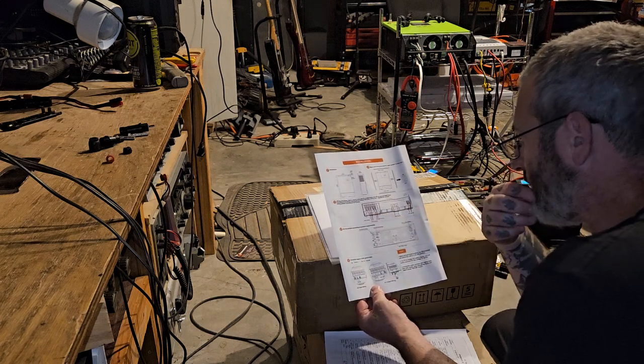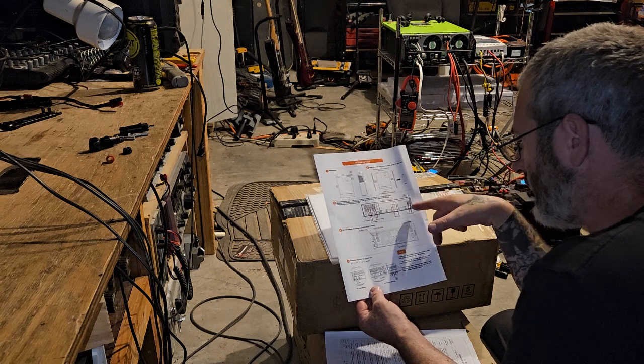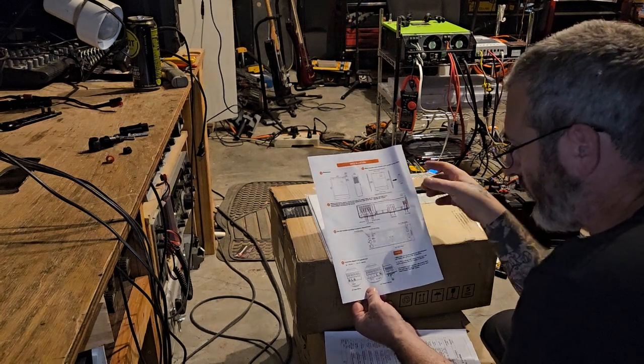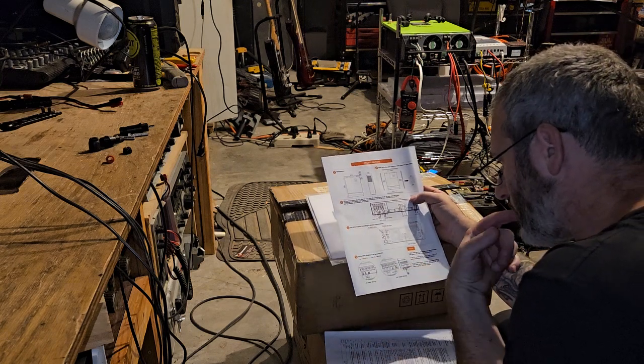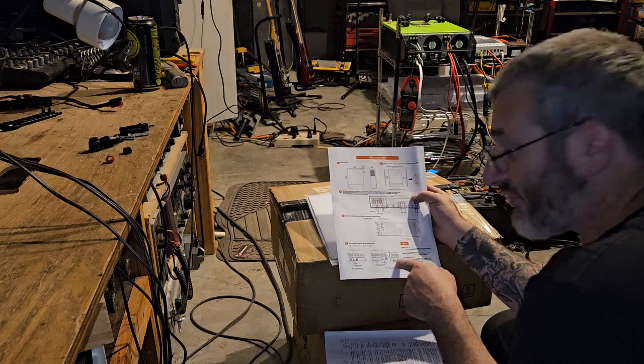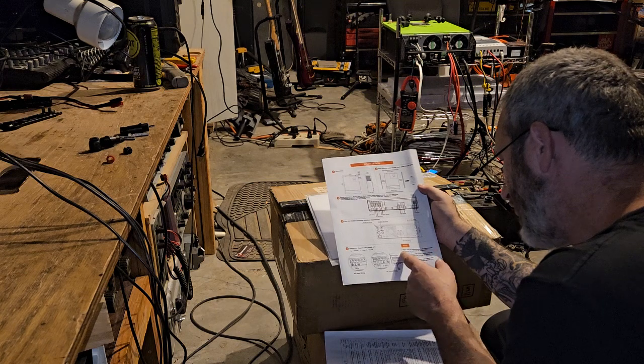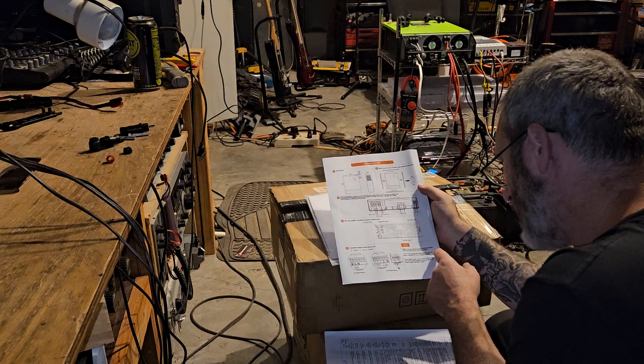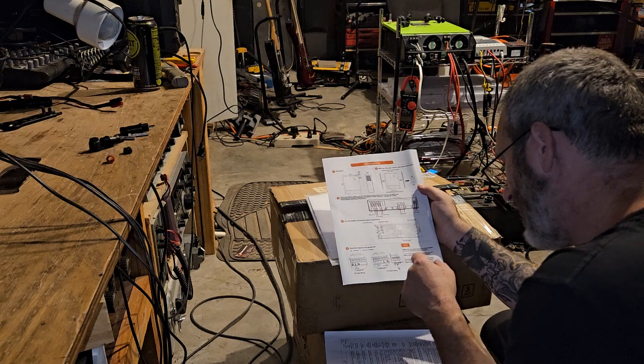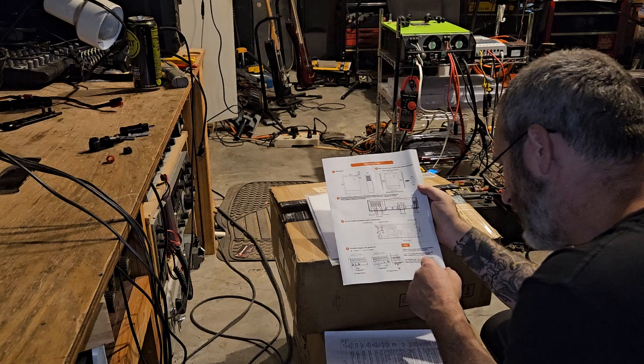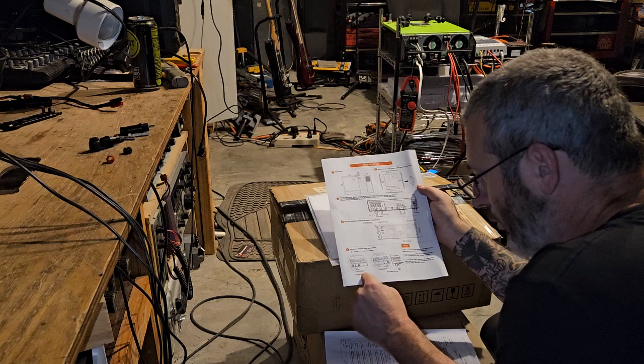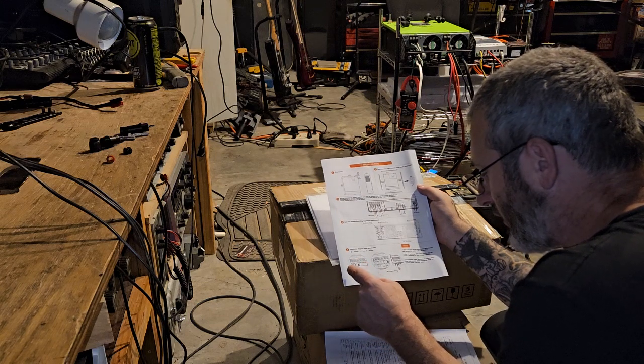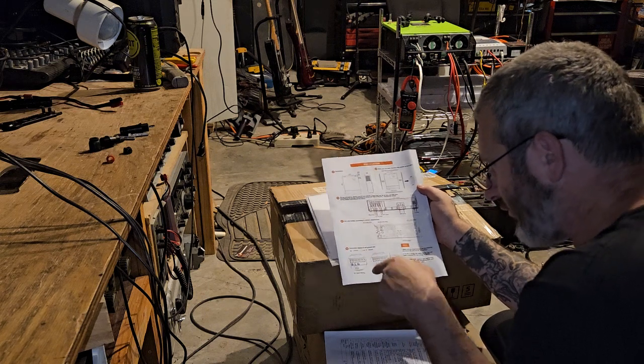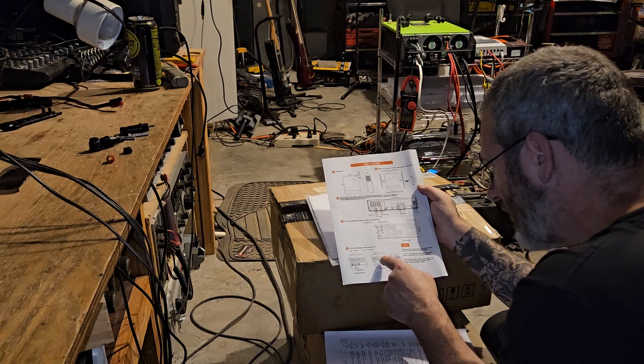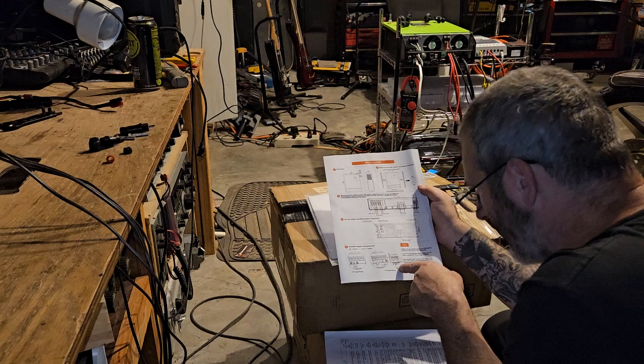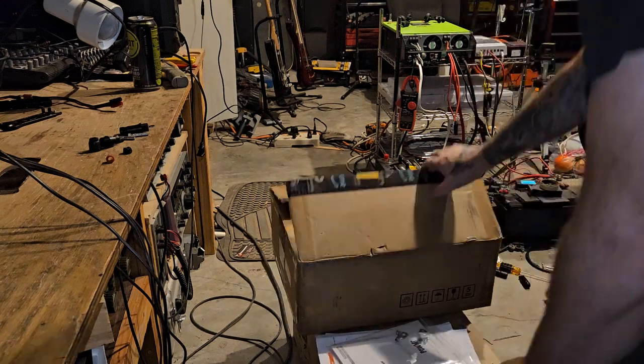But there's a ground for the in, and notice that on a lot of these, they have, which is nice, 2 connectors for the PV. It says AC output. It shows the ground here. I guess you're supposed to use the case ground. Make sure any circuit breakers are disconnected. Ensure the unit is in the off position. For PV to charge 24 volt battery banks, you will need a minimum PV voltage of 35 volts DC. Connection order. Connect your battery first, then solar panels. When everything is done, you need to press the on-off button. AC input, it shows ground, L, and N. So apparently live and neutral. And it says right here what it is. And it shows it here. And it says AC out, that shows live and neutral, and then right down below it shows a little ground thing. So that's cool. So the manual.